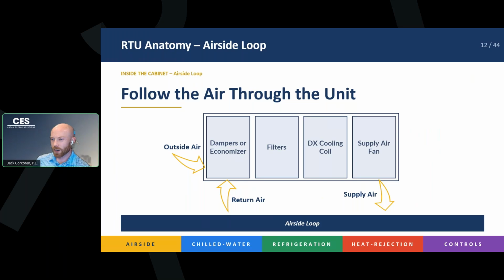So the easiest way to examine a rooftop unit is to follow the air through it, right? If you can imagine this crude looking box is your rooftop unit, you just have 4 sections in this rooftop unit, right? Our air is going to flow in the left side. Our outside air and return air is going to mix. It passes in via the dampers or the economizer. Then it goes over your filters, over your cooling coil, and then your fan is what pushes it back out into the building.